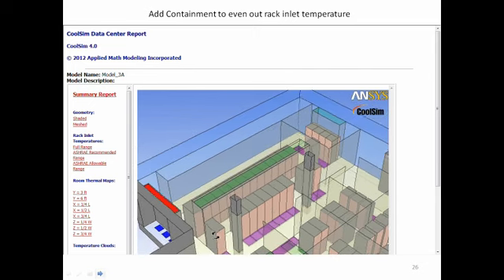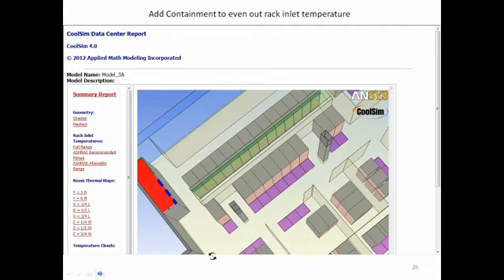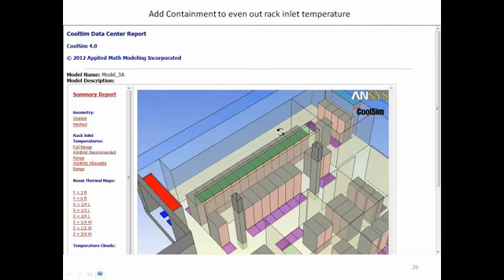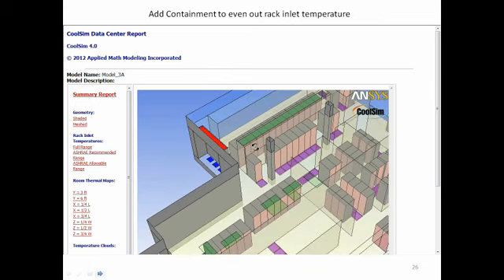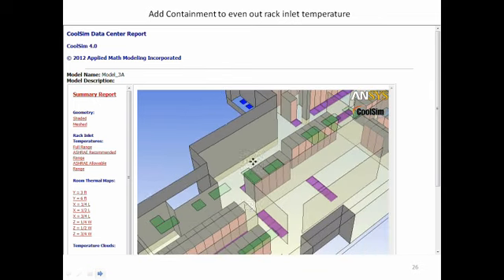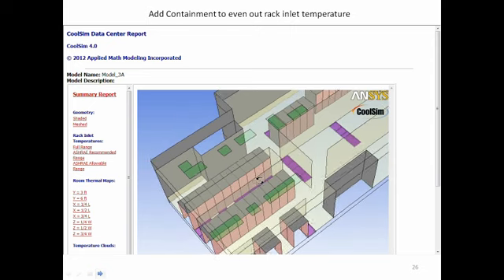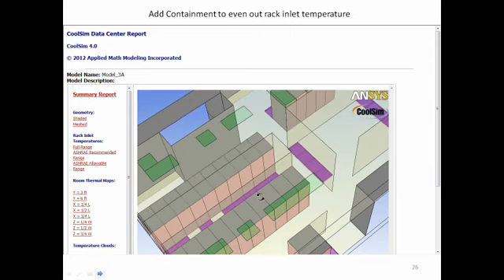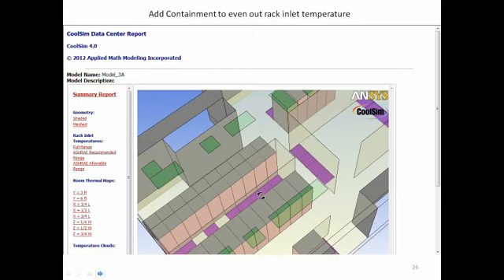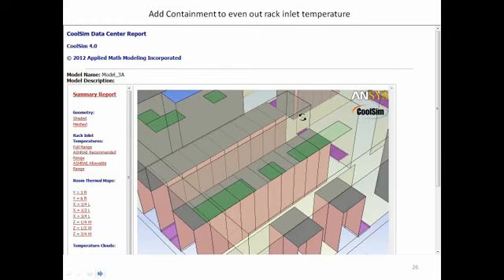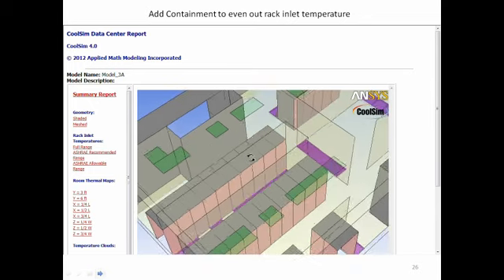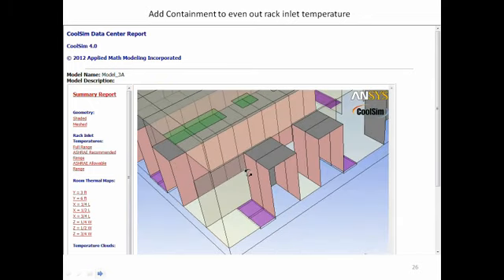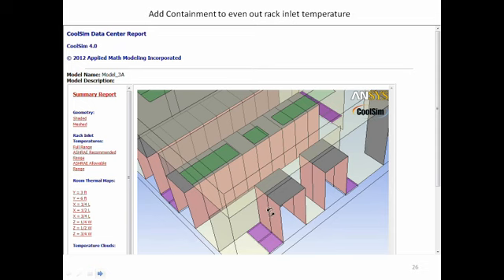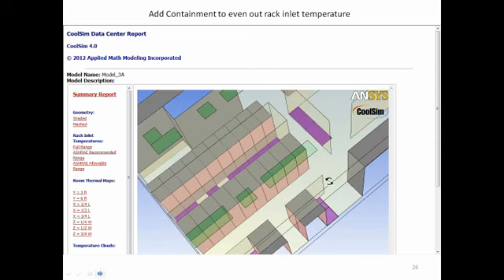To get that distribution of temperature a little more even than what we were just looking at, we can box in this region right here, and you see I've started to do that with these baffles. I've also blocked in between the servers here. Typically in a room you would put curtains; here we're using simple baffles. Down at this end of the room, I did a little bit of work with cold aisle containment. Here we boxed in the racks and put a curtain across the top and across the end. This is a cold aisle, and I'm trying to preserve the coolness there. Also in these corners I put a sheet across and put a little edge on this side of the room.